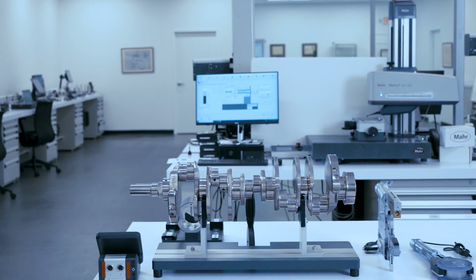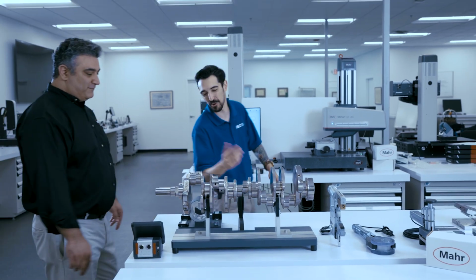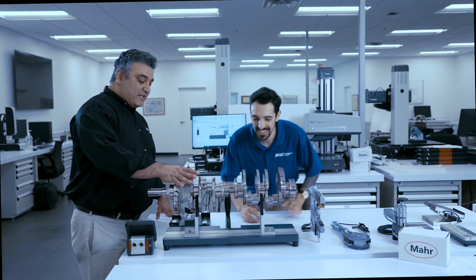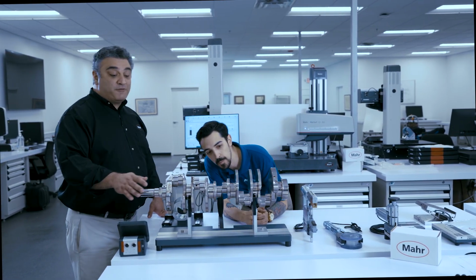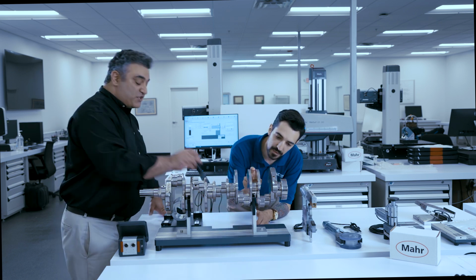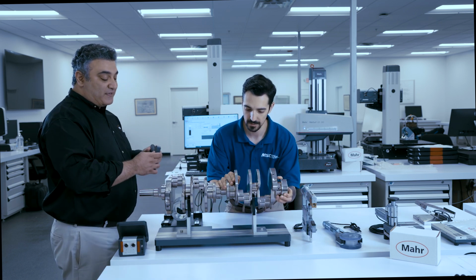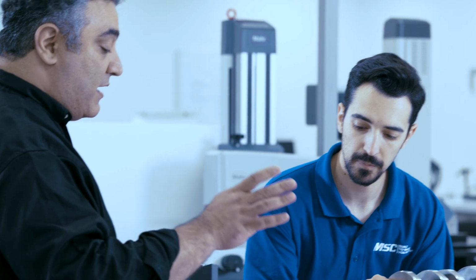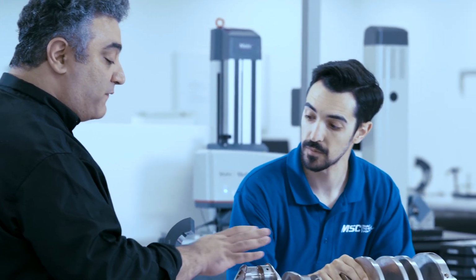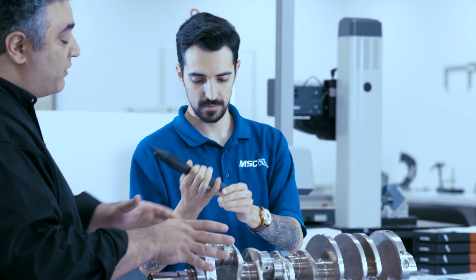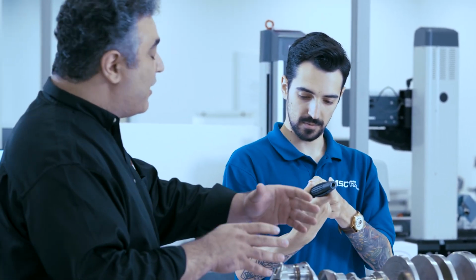All right, man, it looks like we're still in the automotive industry. What do you got for me over here? This is a good example of air gauging. This is a crankshaft, and this gauge here is what we call an air gauge snap, an air snap. Perfect gauge for this type of tool where you want to check the part while it's still on the machine.